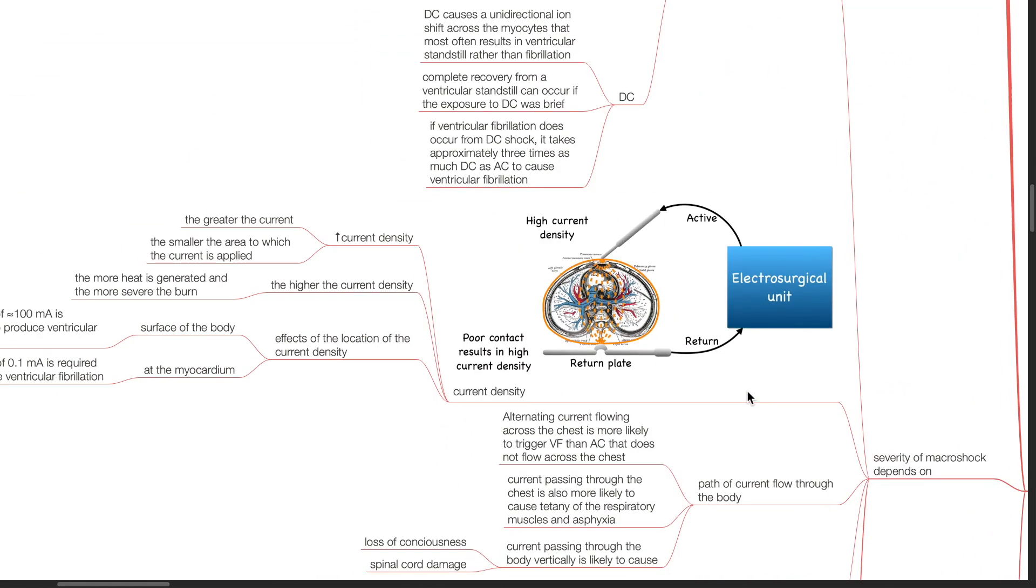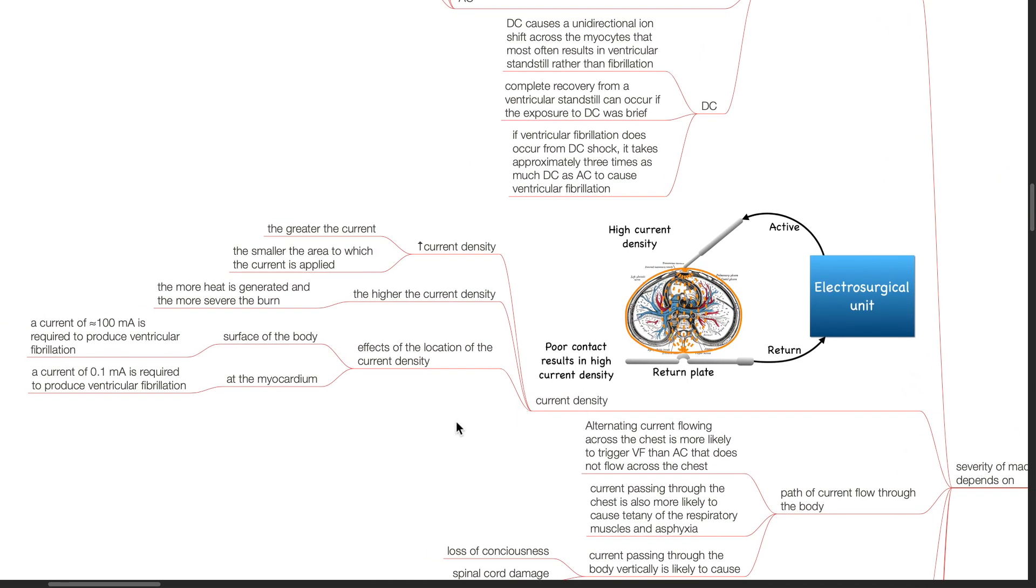Current density is increased the greater the current and the smaller the area to which the current is applied. The higher the current density, the more heat is generated and the more severe the burn. Effects of the location of current density: if it is on the surface of the body, a current of about 100 mA is required to produce ventricular fibrillation. However, if the current density is at the myocardium, only a current of 0.1 mA is required to produce ventricular fibrillation.